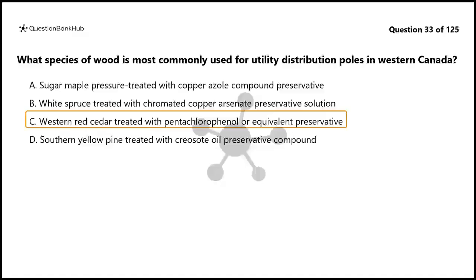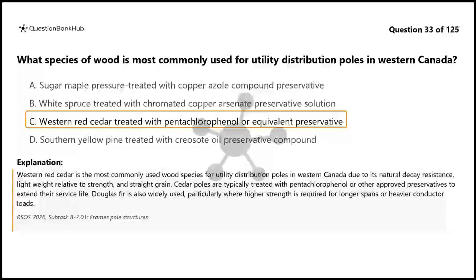The correct answer is C. Western red cedar is the most commonly used wood species for utility distribution poles in Western Canada due to its natural decay resistance, light weight relative to strength, and straight grain. Cedar poles are typically treated with pentachlorophenol or other approved preservatives to extend their service life. Douglas fir is also widely used, particularly where higher strength is required for longer spans or heavier conductor loads.